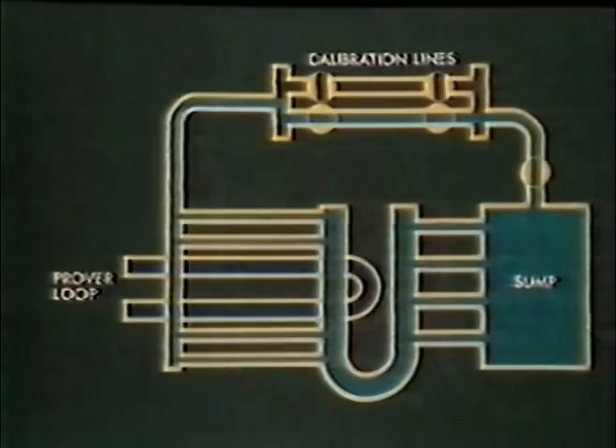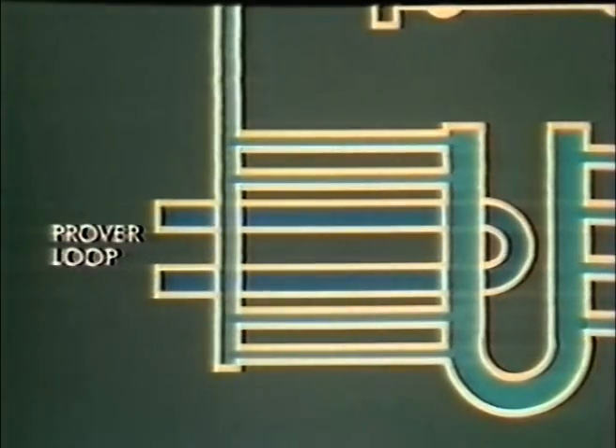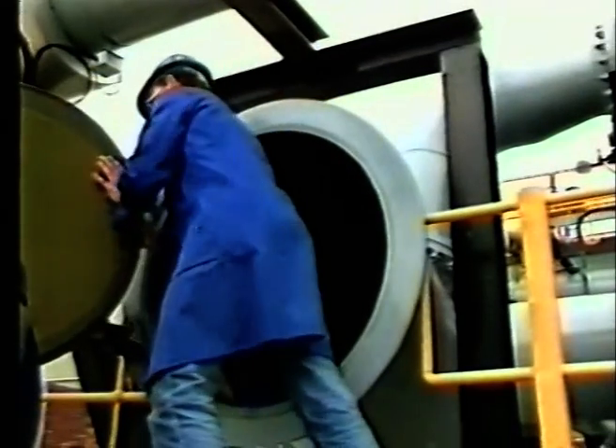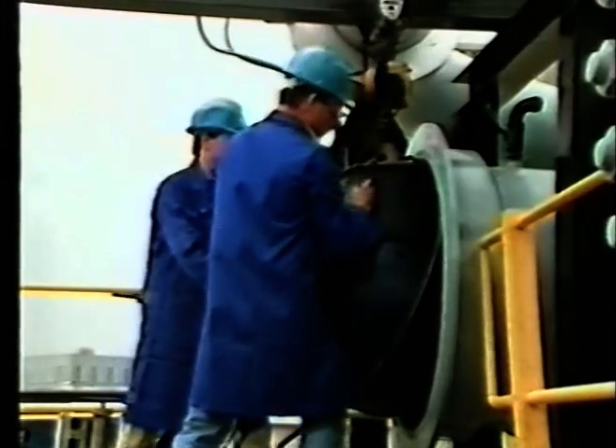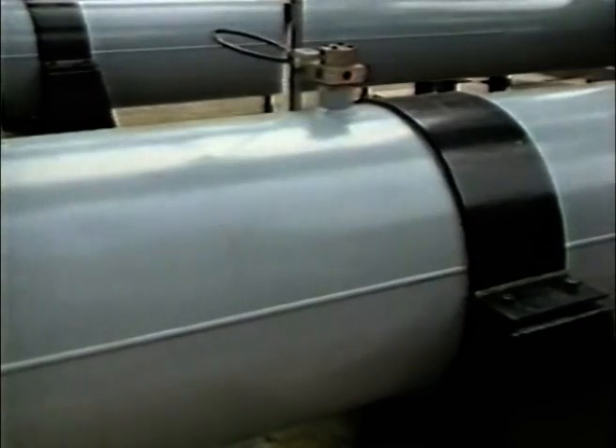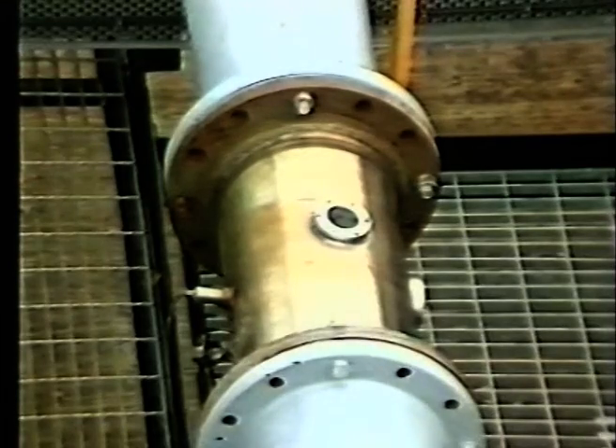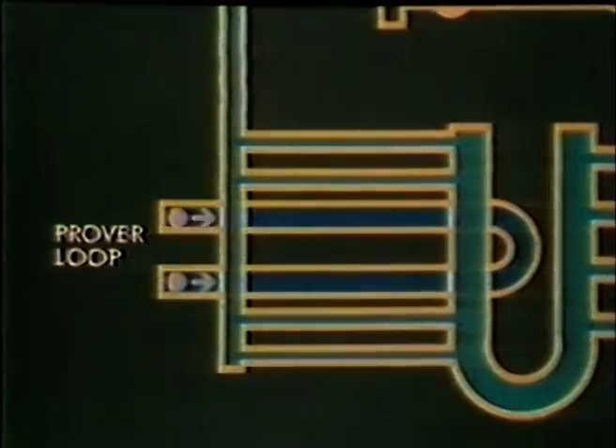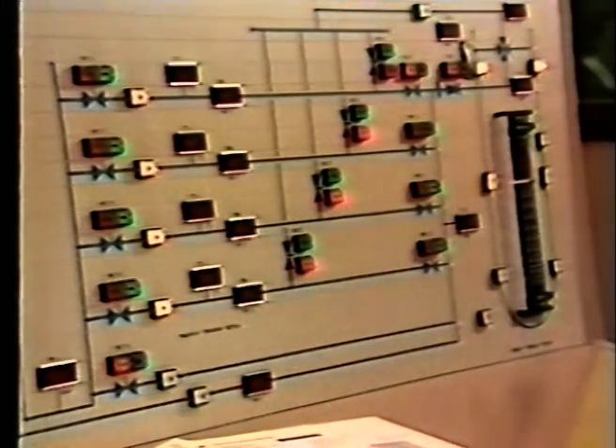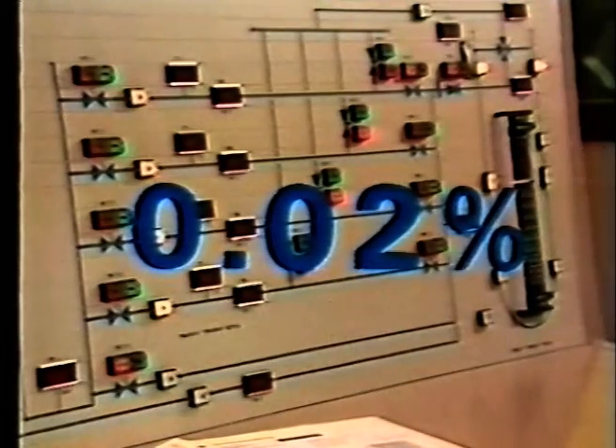That's all very well, you might say, but how do we know that the reference standard turbine meters are accurate? A fine point, and one that's not lost on Kent's designers, which is why the system incorporates a high-precision mechanical displacement meter prover. In testing the accuracy of the reference meters, a liquid-filled plastic sphere is passed through a prover loop, activating detectors which tell the computer when the sphere has swept out a precisely known volume of water, which has also been passed through the reference flow meter. The prover loop test is conducted in both directions, and the computer stores the relevant data for comparison against the meters or valves under test. To ensure the greatest accuracy, up to 5 consecutive calibration runs are performed within extremely close tolerances to establish the meter coefficient at regular intervals. The prover loop is calibrated by an approved independent authority.